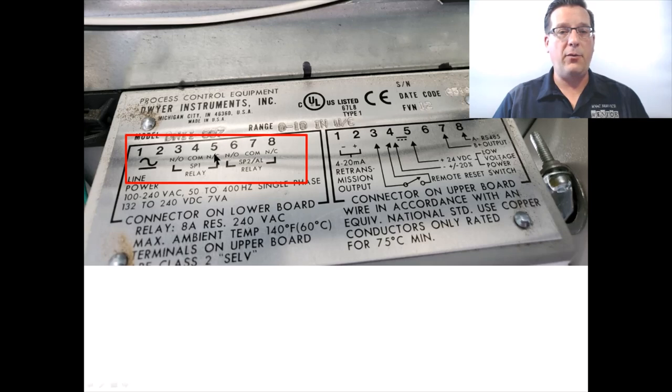There happen to be two of those. There's SP1 and SP2. SP2 is typically going to be used as an alarm, which is indicated by the AL, the SP2 slash alarm relay contacts. So that when we reach a certain pressure, we can close or open a set of contacts that can either create an alarm of either rising pressure or falling pressure. That's what that's used for. So here we have seven is the common terminal, eight is the normally closed terminal, and six is the normally open terminal. So terminal six and terminal eight share terminal seven in common with one another. Notice that terminals three, four, and five have absolutely nothing to do with terminal six, seven and eight. Nothing in common whatsoever.